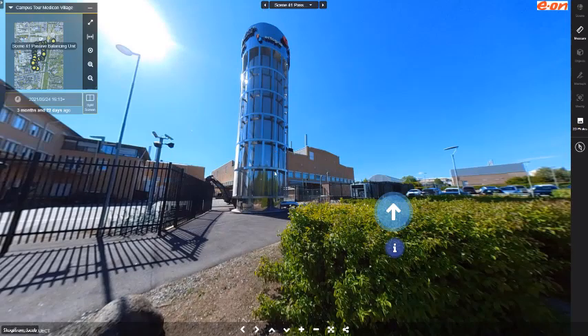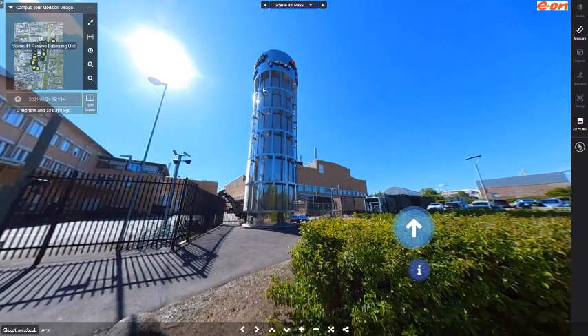Helen was talking about how this is working, and you can see it as a storage for both heating and cooling, where the heating is stored at the top of the tank and the cooling is stored at the bottom. Two pipes go in: one at the bottom, connecting to the cold side and cold flow, and the other going into the tank at the top. We also have temperature sensors to know where the level between heating and cooling is inside the tank.